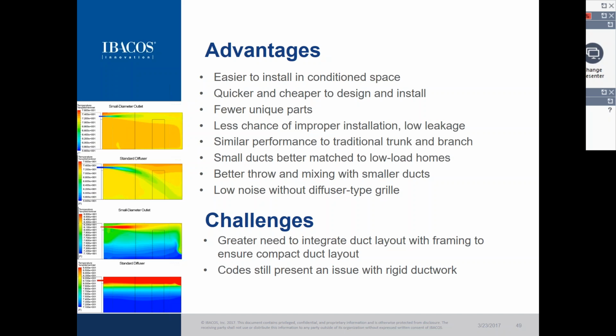There's certainly a bit of concern that if you have higher velocity air coming out of a small outlet, it might impinge upon an occupant somewhere, but that's where good design and these high sidewall types of outlets come into play—air is typically mixed across the top of the room, then mixing down and providing even comfort throughout the space, not blasting some occupant with a jet of air. That's something we've looked at in the past, and these small diameter outlets, when done correctly, can actually provide really good mixing and throw.